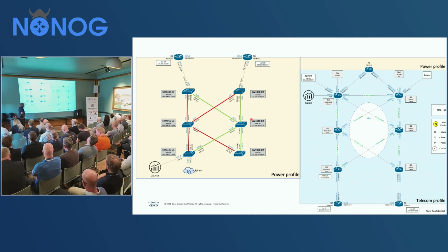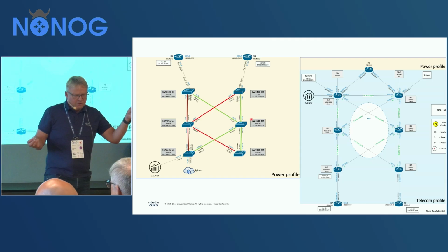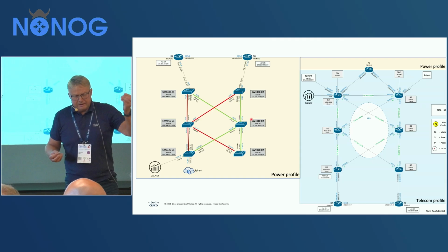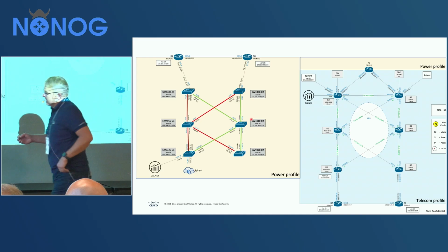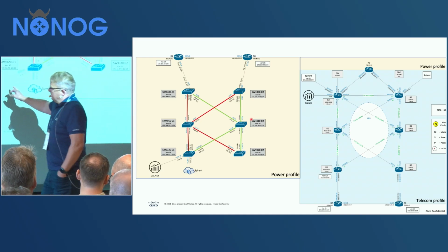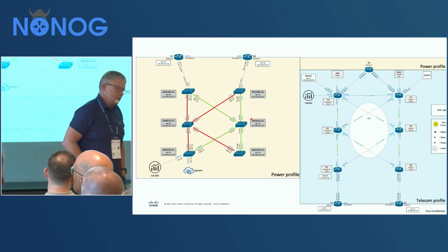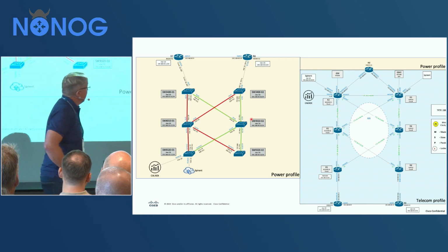To be able to measure this, if you're going to test this, there is a device here and a device at the top. We are using Calnex. Calnex is measuring the time that is inserted at the grandmaster, being a client at the grandmaster, and measuring all the way down to the substation here. By doing so, we can then see how good the clock quality is.